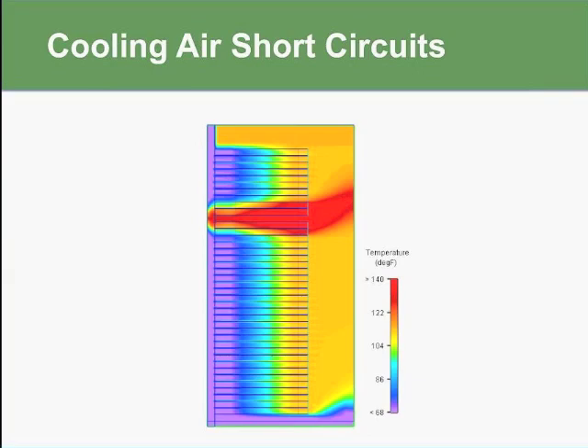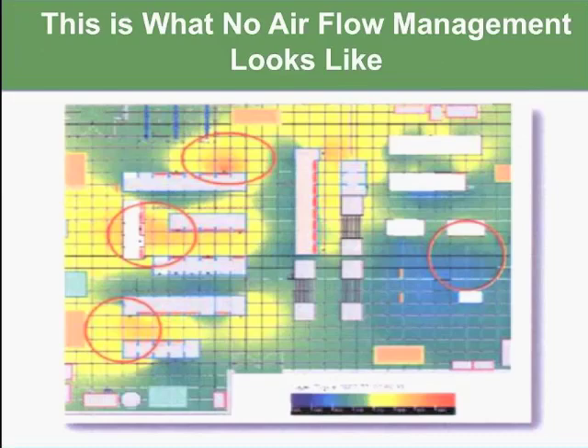This is another graphic, a heat map showing what happens when you have cool air short-circuiting. So in this case, you can see this is probably either a missing blanking panel where you have a gap in the rack where you don't have a piece of equipment, so you're short-circuiting the hot air into the cold air aisle, or it could just be that someone had put a toaster in this space and you're seeing the heating going into the cold aisle section. But either way, it's very inefficient and it's not helping to cool your servers. But it's good to have that visibility to see that that's happening because maybe nobody notices it otherwise.